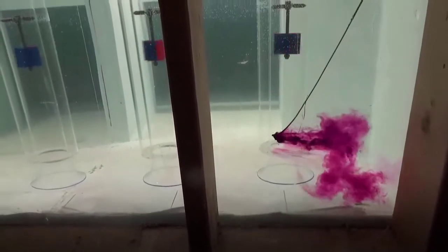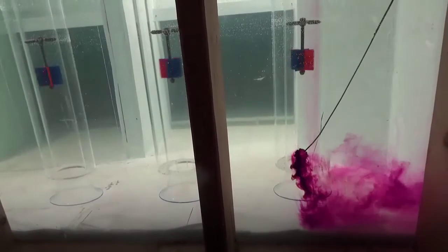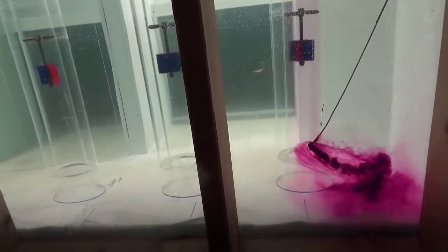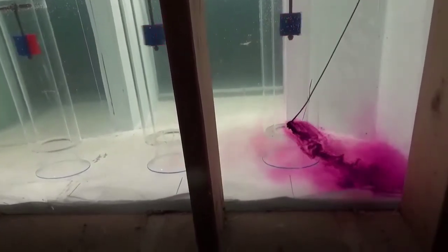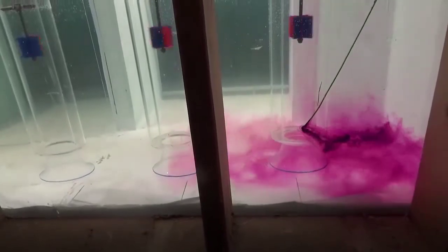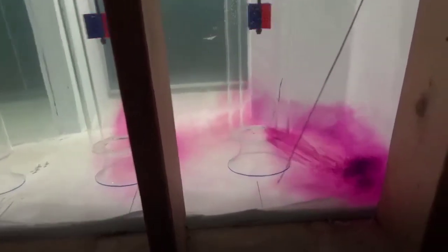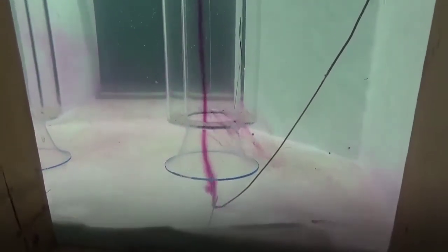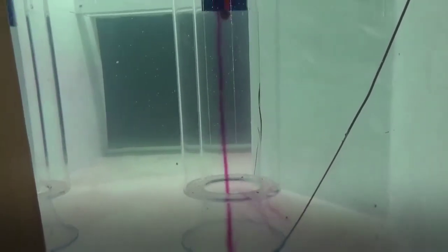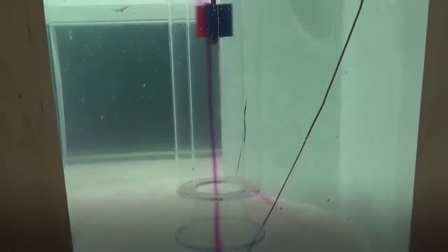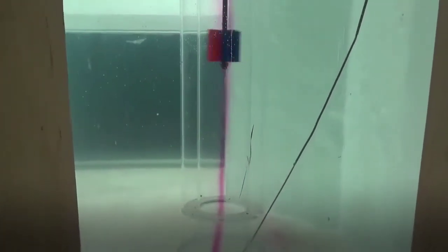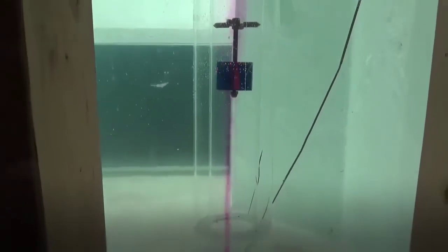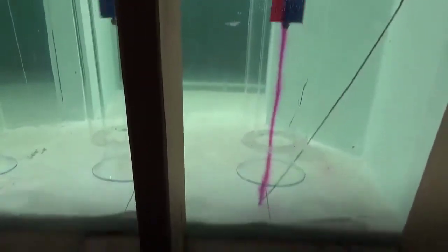See this sideways flow again? We were talking about that, it'll go down, then it'll go sideways here. That's that circulation around the back. It's creating a very, very strong floor vortex. You can see right here going up in. It's extremely organized. That's happening under all the pumps. It's contributing to the pre-swirl, but so is the circulation. The extent of which we're going to find out when we mitigate that.